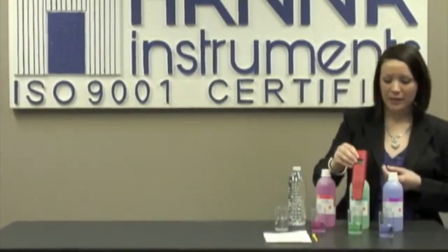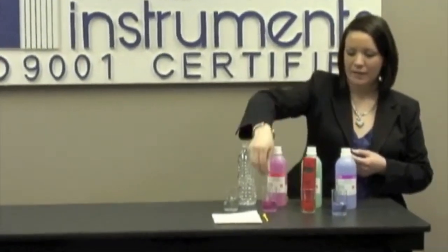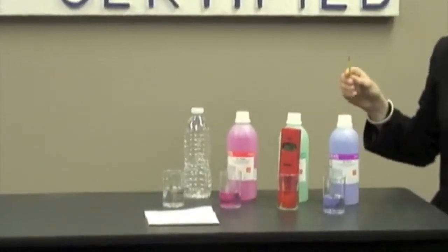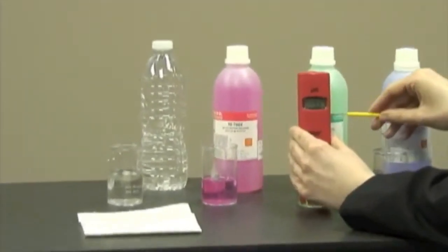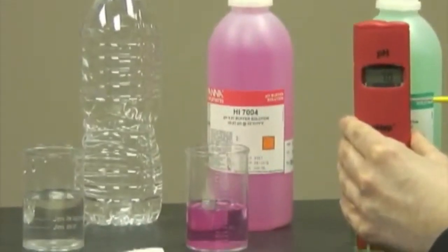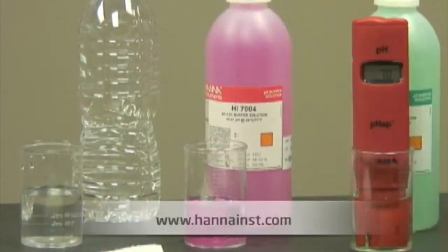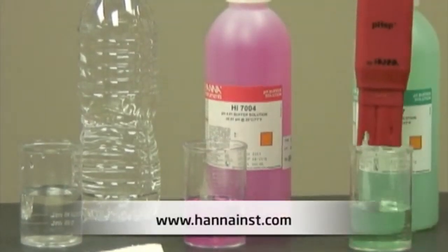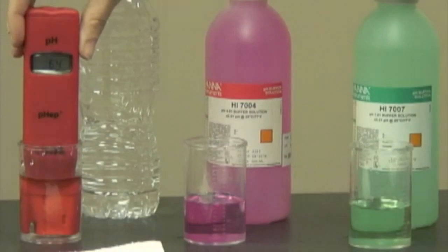So I'm going to turn the instrument on, I'm going to put it in the pH 7 buffer, and then I'm going to take my calibration screwdriver and turn it until it reaches a pH of 7.